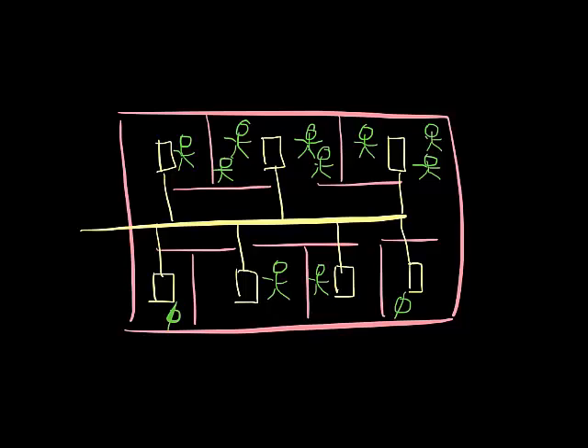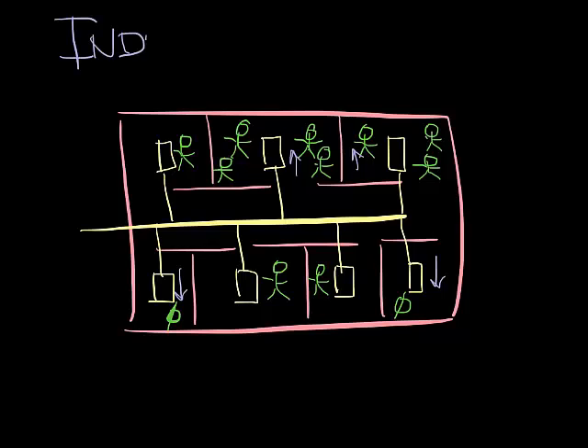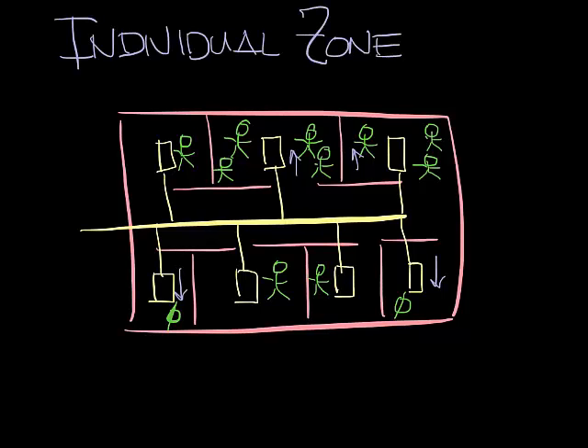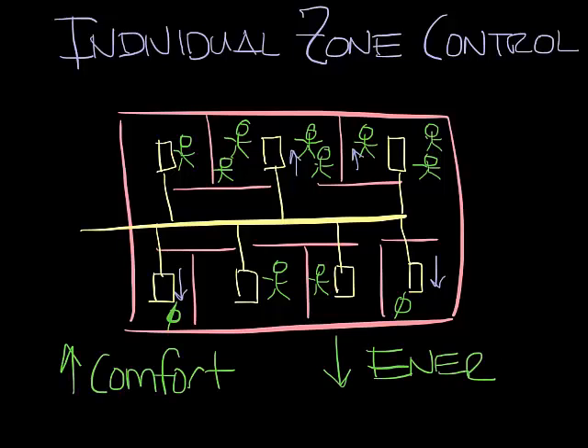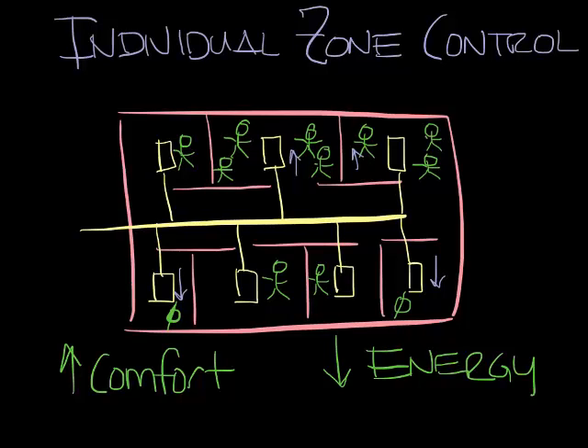Because there are a lot of people in one area, it will need more air, but another area may be empty so it needs less air, and so on throughout the building. Instead of the building having the same amount of air everywhere, the VAV boxes will allow you to have individual zone control. This increases comfort in each area and reduces the energy use of the building because the HVAC system can adjust the airflow to match the building's needs.